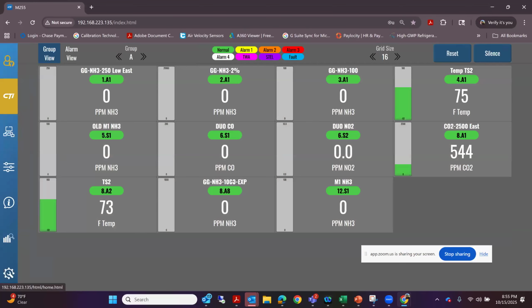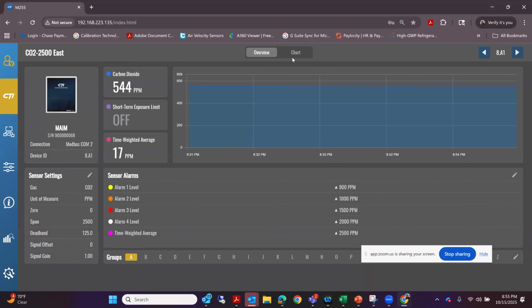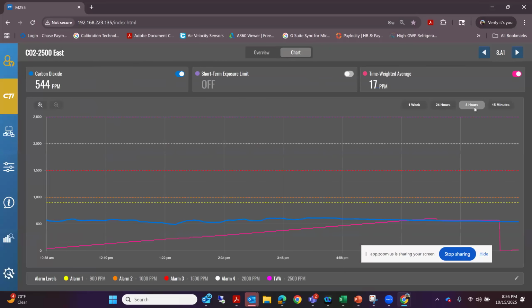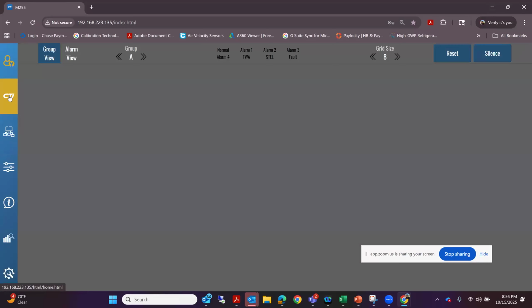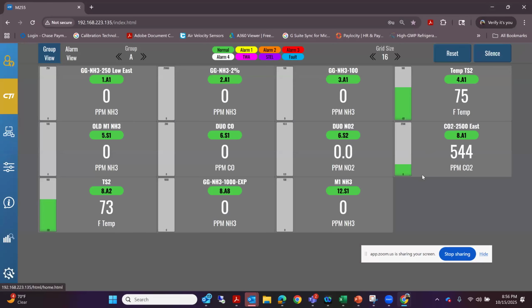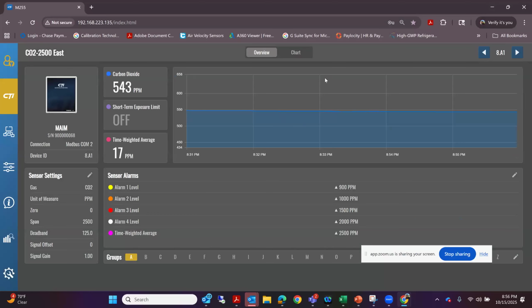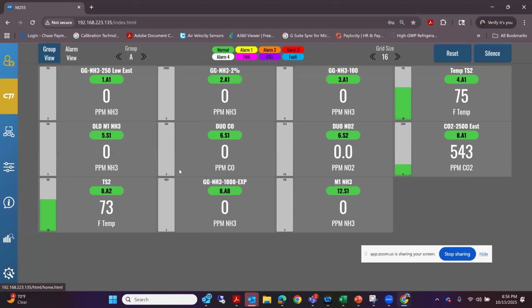And when you're setting them up, you've got trend lining. I blew into this earlier today, 8 hours ago. I guess it's been a little ways there. So we have some pretty good trend lining from where I was having them blow into that CO2 sensor out there at the CTI office. I've got a guy that sits right around the corner there, and I'll tell Randy, go run around the corner and breathe into that 0 to 2,500 sensor, and you'll just see this thing start climbing up, and you'll see all these colors come across the screen at those alarm set points when this raises up. It's pretty neat looking. Usually he's not there tonight, or I'd have him go do it. But unfortunately, he's not going to be hanging out at the CTI office this late.